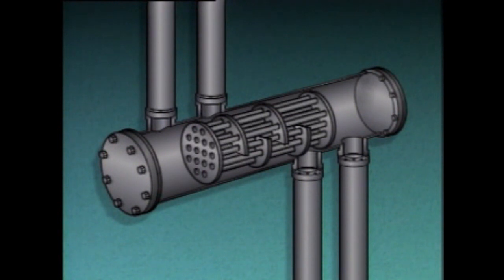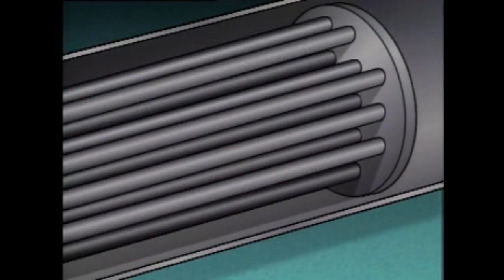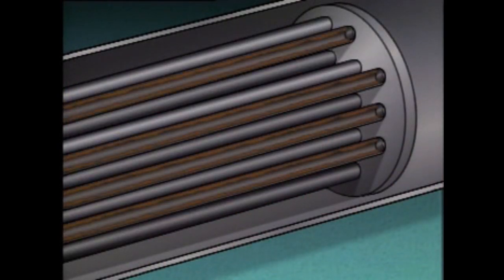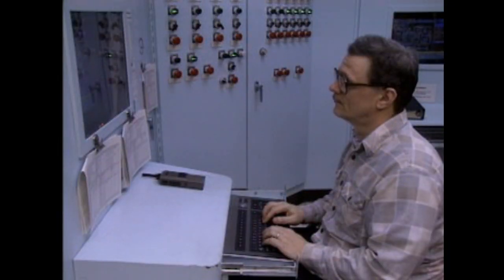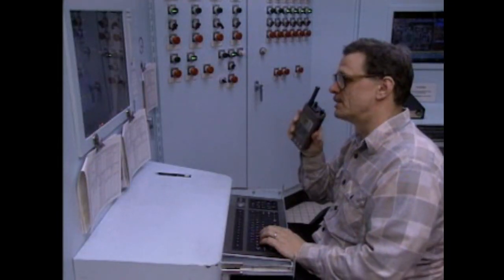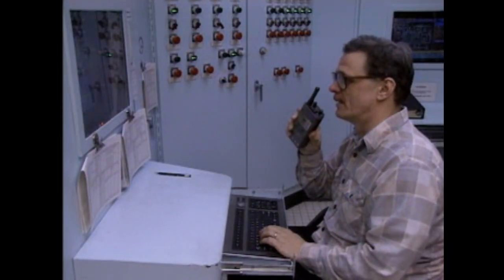For example, if the delta T across the tube side of a heat exchanger is supposed to be 10 degrees, but it is only 5 degrees, it could be an indication that the tubes in the unit are becoming fouled, or that one or both of the flow rates are not correct for proper operation. In any event, the cause of the problem should be investigated, and supervisory personnel should be informed.